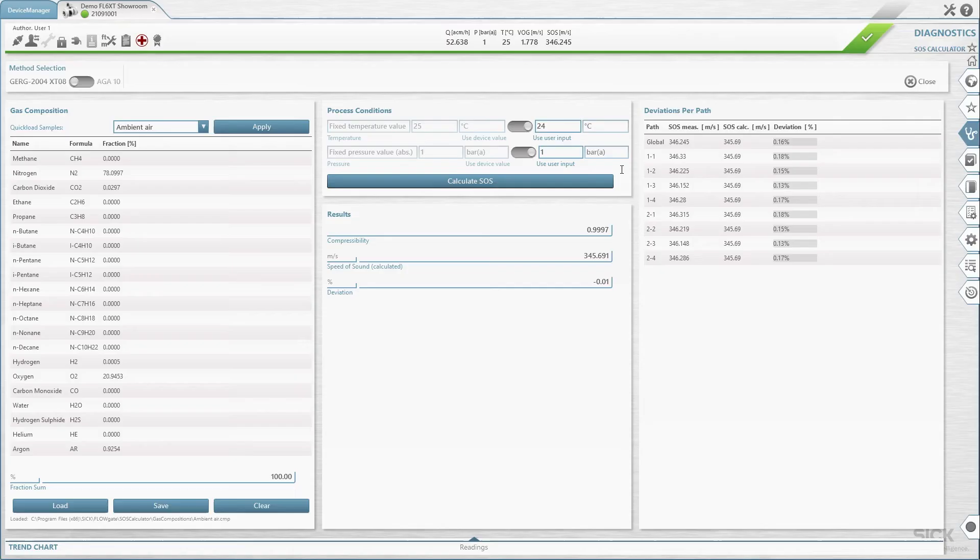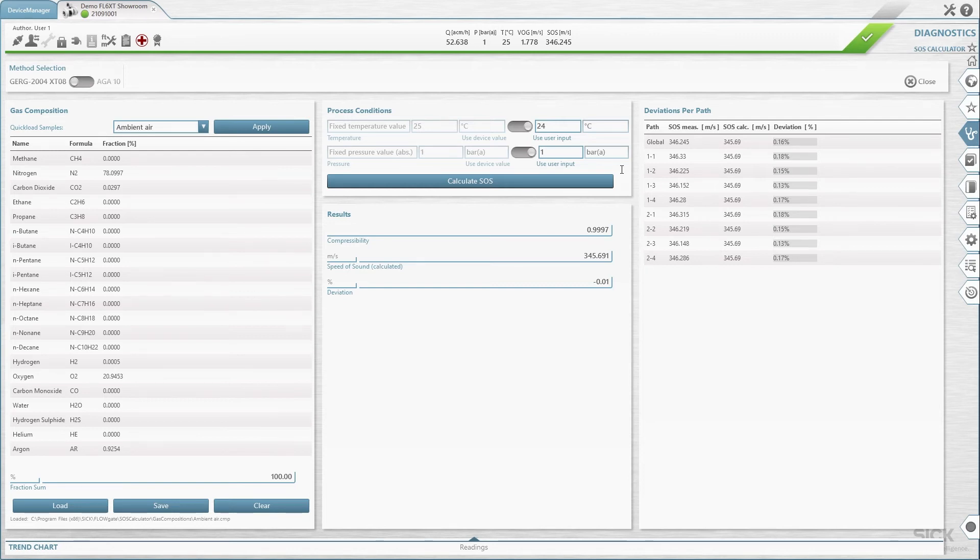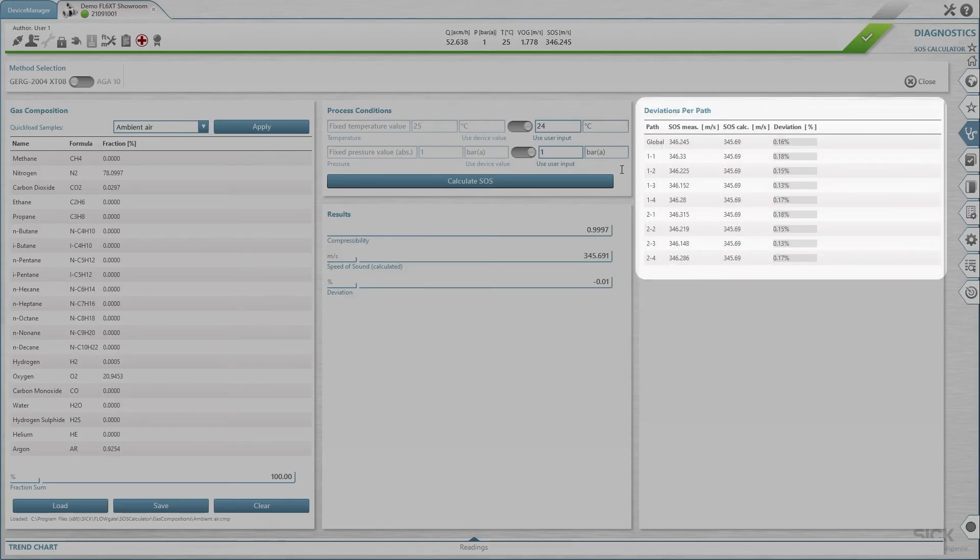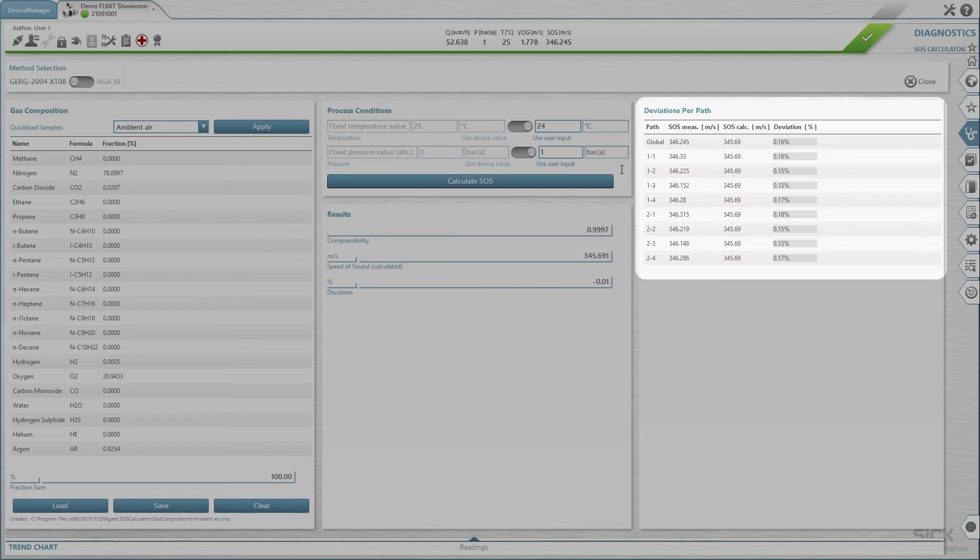Once you have run the theoretical speed of sound calculation, you can compare the result with the connecting meter's current measurement results for each measuring path. The panel deviation per path displays the deviation from the calculated theoretical speed of sound for each path.